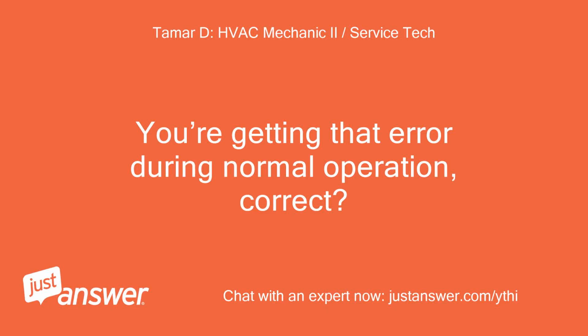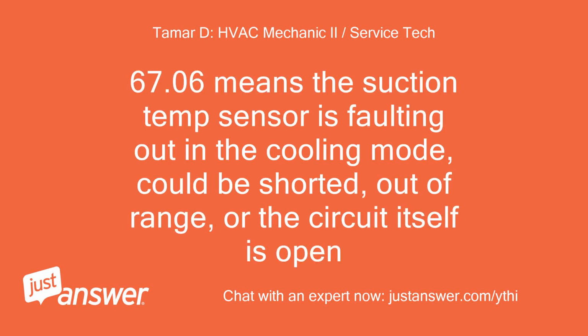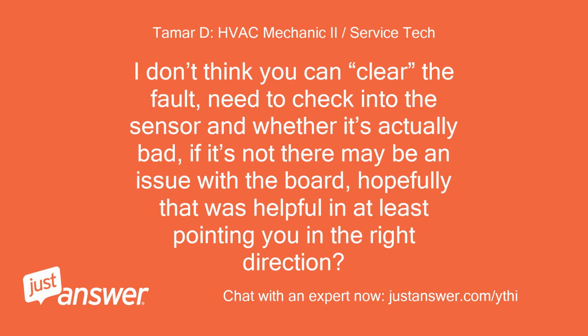You're getting that error during normal operation, correct? 67.06 means the suction temp sensor is faulting out in cooling mode, it could be shorted, out of range, or the circuit itself could be open. I don't think you can clear the fault. You need to check into the sensor and whether it's actually bad. If it's not, there may be an issue with the board. Hopefully that was helpful and at least pointed you in the right direction.